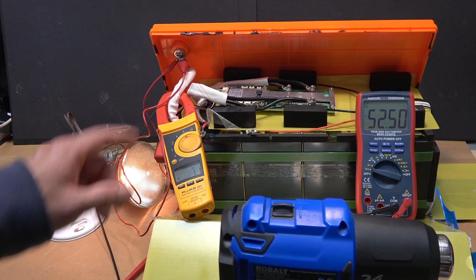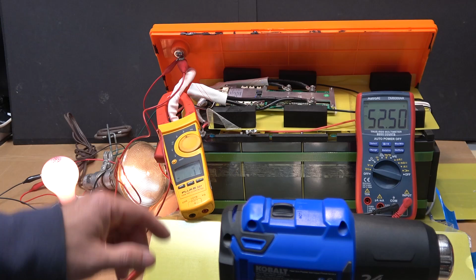Let's try an overheat protection test. The BMS should turn off when the battery is hot enough. I'm going to use my heat gun to heat up the sensors, and I use aluminum foil to wrap around the sensor so that my heat gun does not melt the sensor.